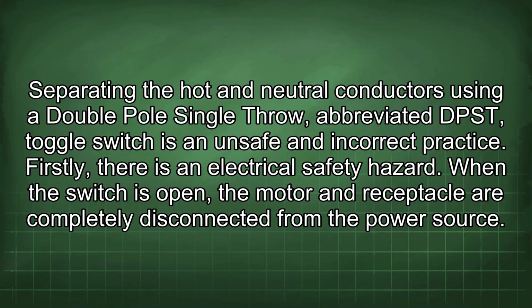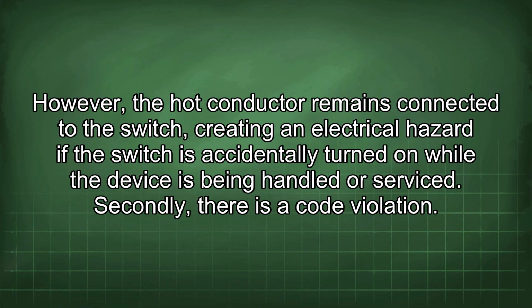Separating the hot and neutral conductors using a double-pole single-throw, abbreviated DPST, toggle switch is an unsafe and incorrect practice. Firstly, there is an electrical safety hazard. When the switch is open, the motor and receptacle are completely disconnected from the power source. However, the hot conductor remains connected to the switch, creating an electrical hazard if the switch is accidentally turned on while the device is being handled or serviced.